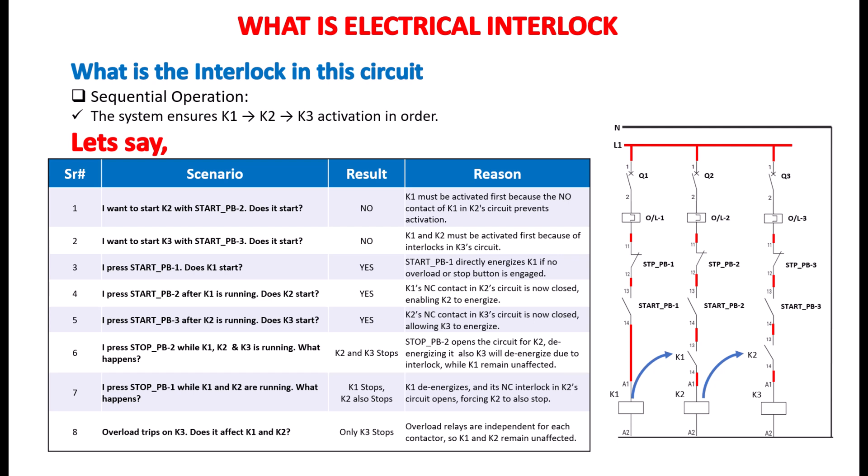Scenario 1. If I want to start K2 by pressing START PB2, will it start? No, it's not. Why? Because K1 must be running first. There's an interlock, a normally open contact of K1, that prevents K2 from activating until K1 is energized.